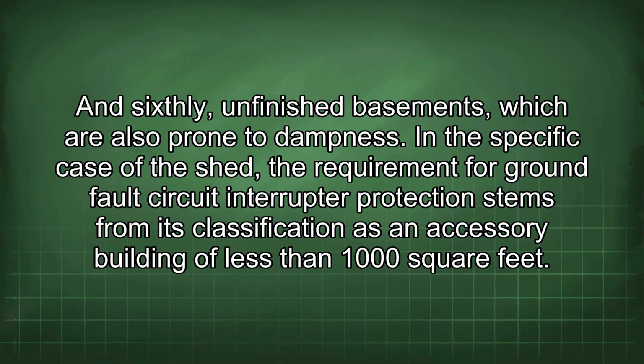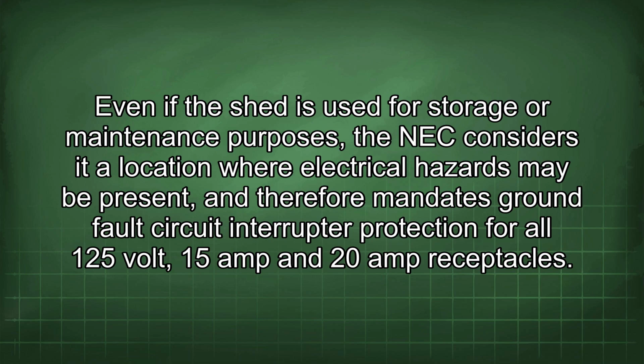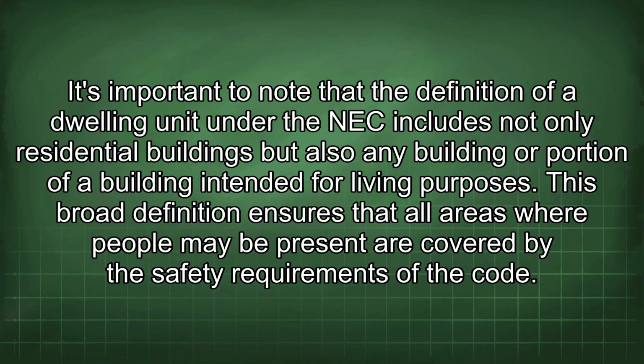In the specific case of the shed, the requirement for ground fault circuit interrupter protection stems from its classification as an accessory building of less than 1,000 square feet. Even if the shed is used for storage or maintenance purposes, the NEC considers it a location where electrical hazards may be present and therefore mandates ground fault circuit interrupter protection for all 125-volt, 15-amp and 20-amp receptacles. It's important to note that the definition of a dwelling unit under the NEC includes not only residential buildings but also any building or portion of a building intended for living purposes. This broad definition ensures that all areas where people may be present are covered by the safety requirements of the code.